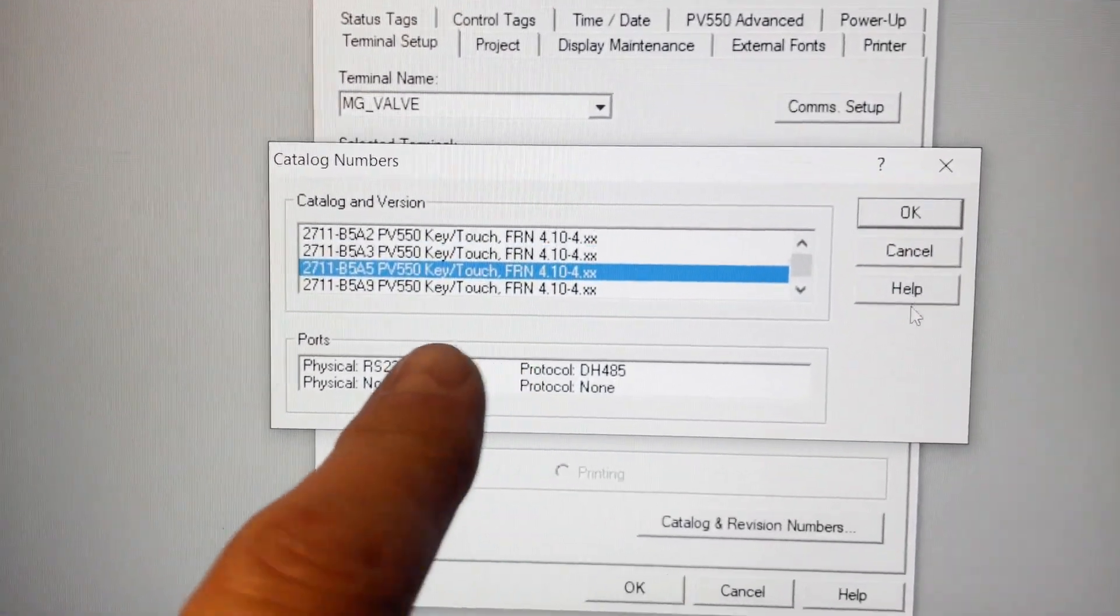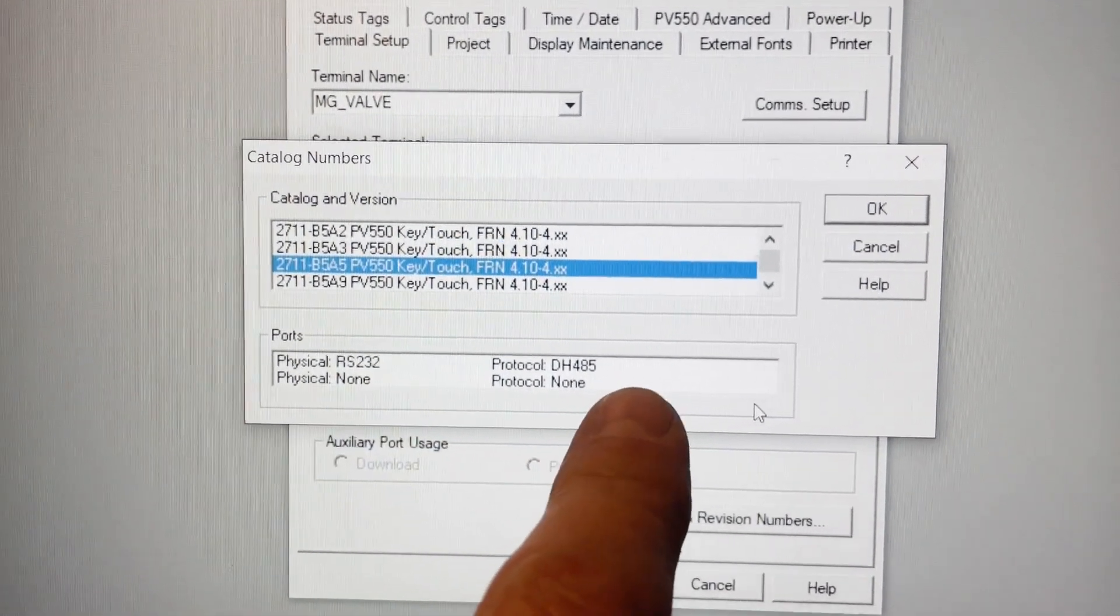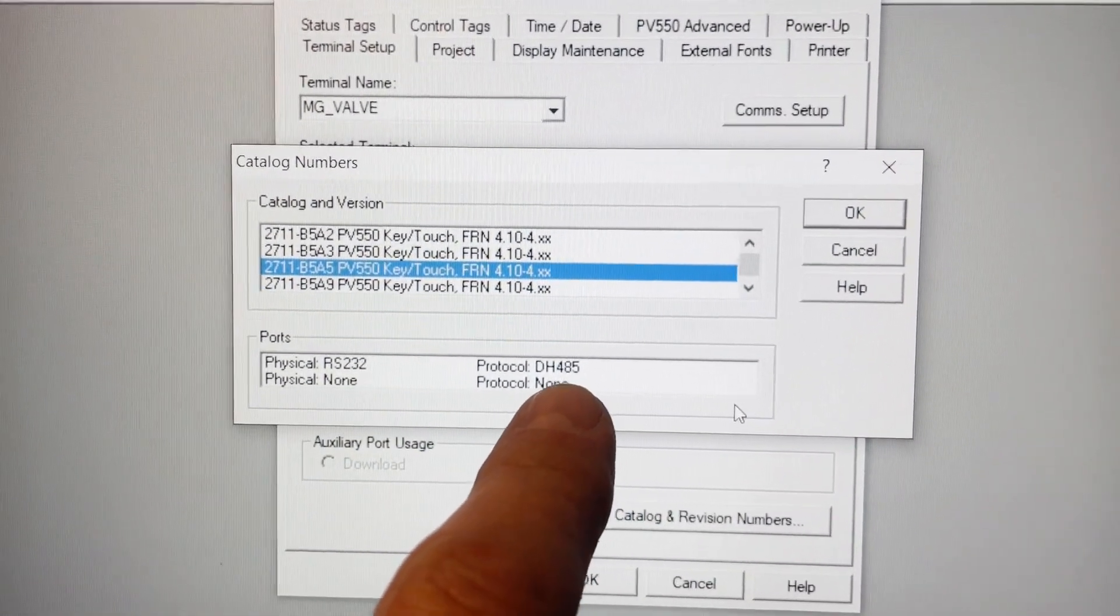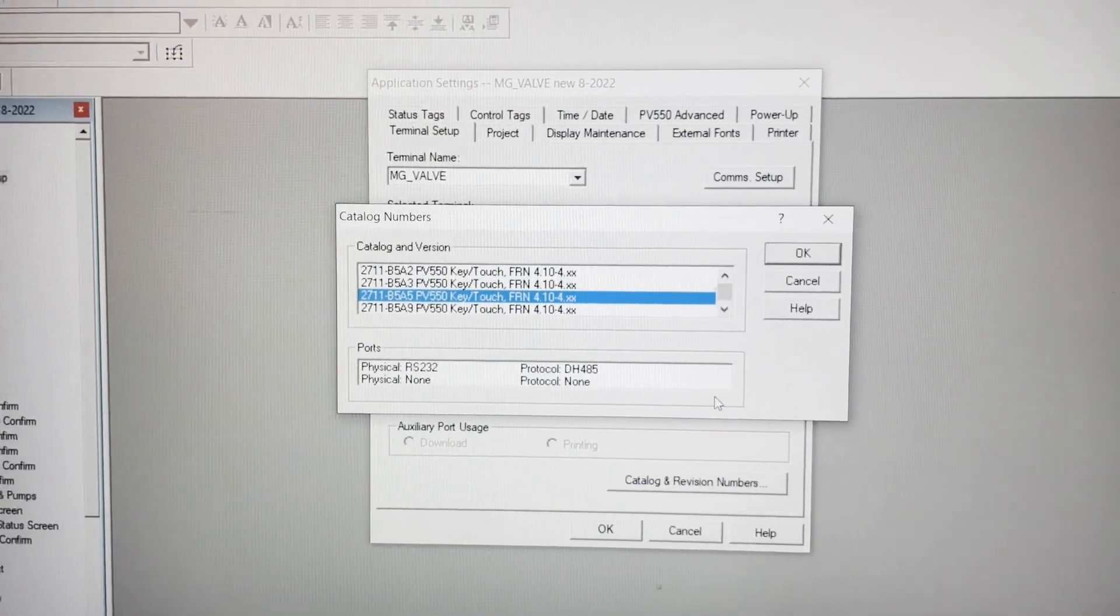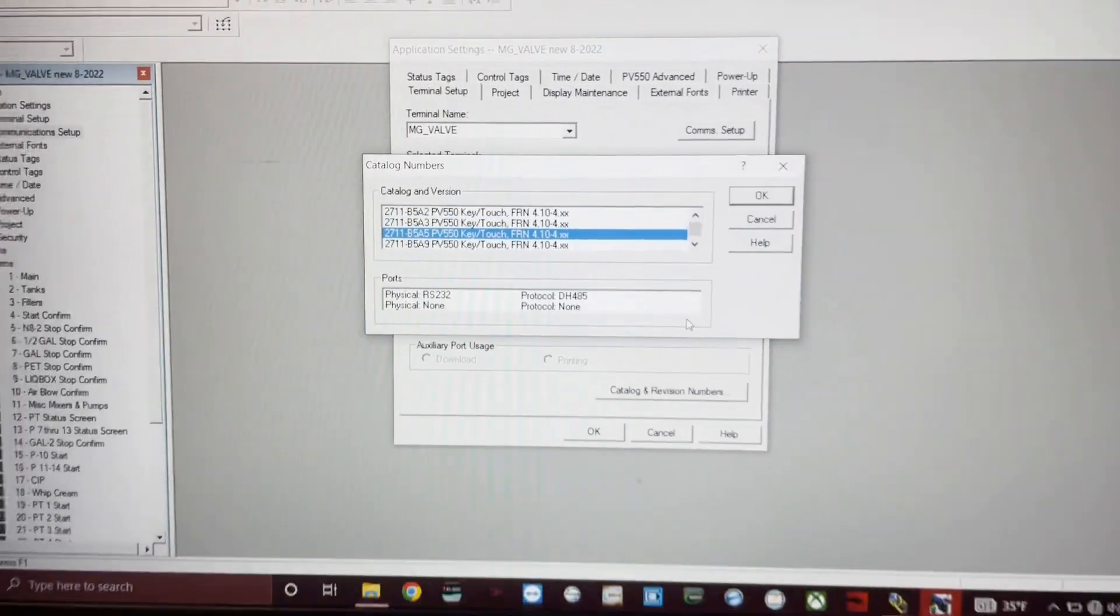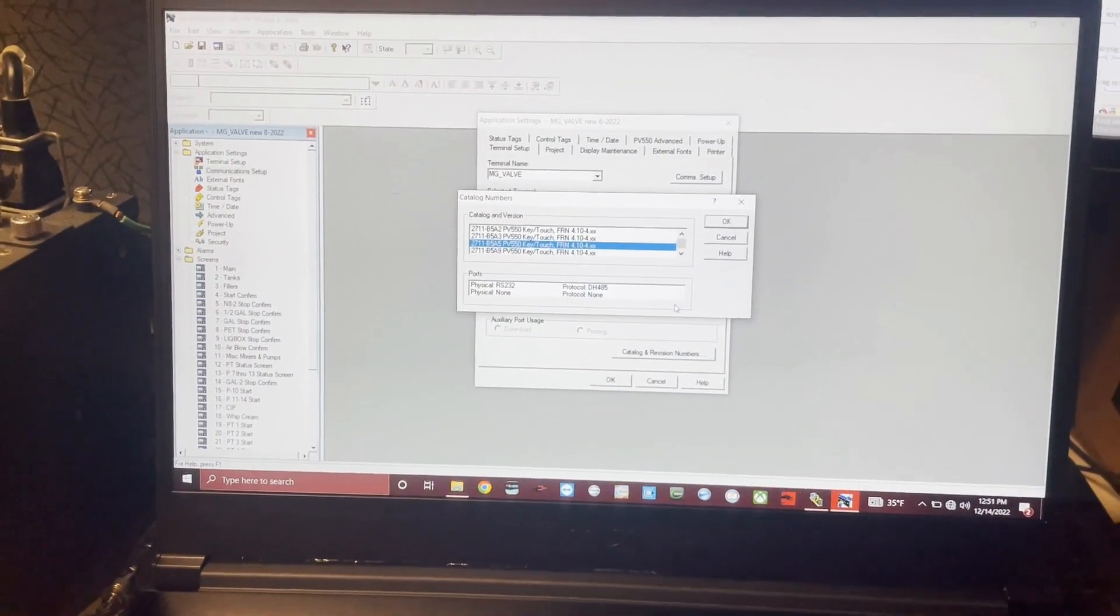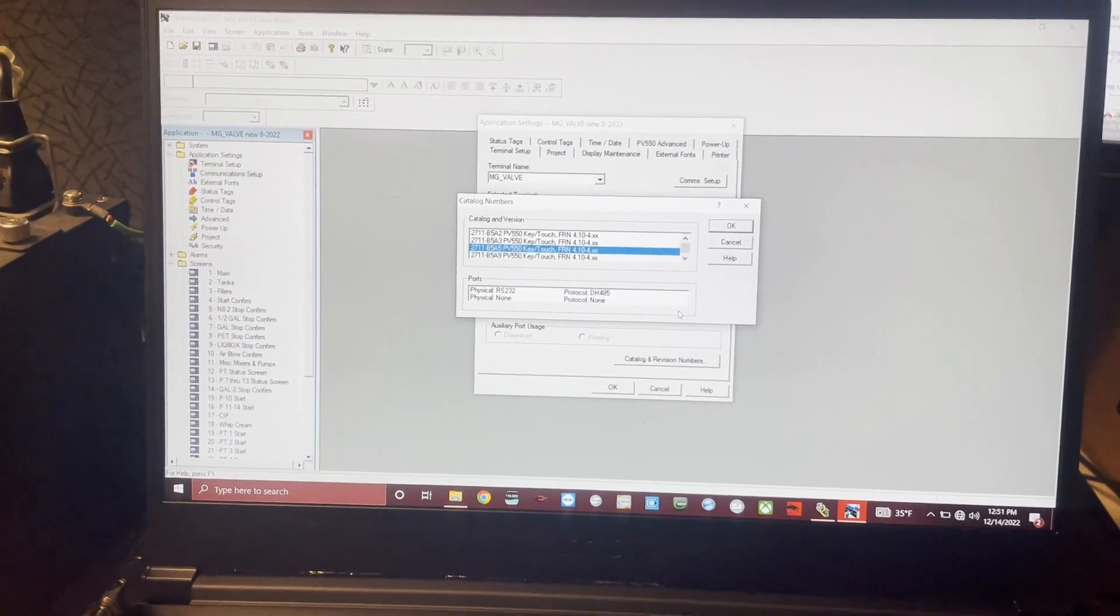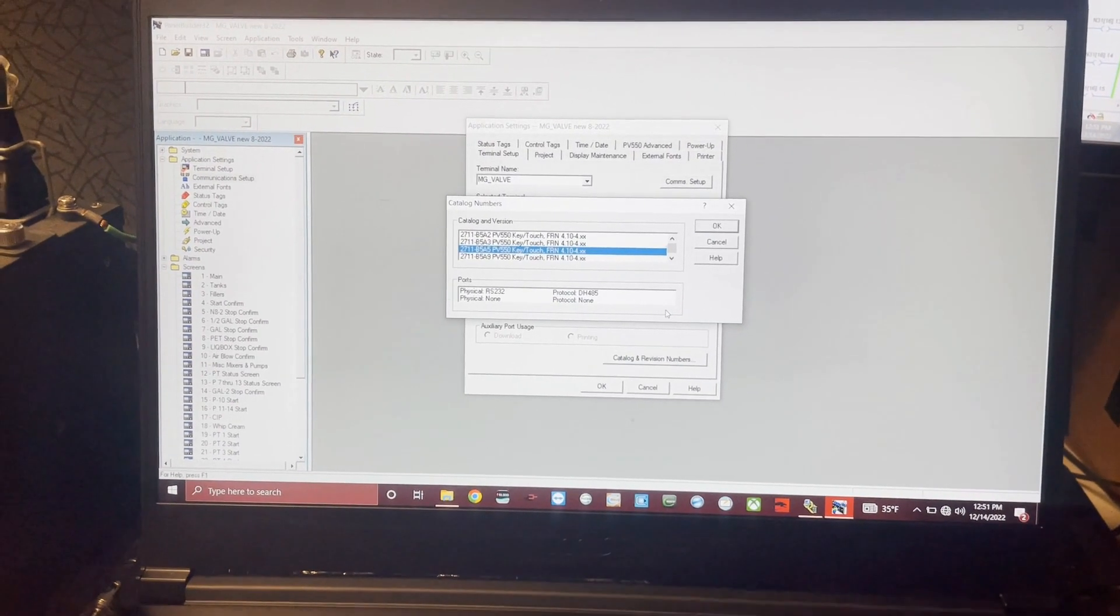You can see down here the physical port is RS-232. The protocol is DH-485, and the 550s are a little bit different if you're trying to use this. This is a Windows 10 machine, and we're going to go through what you need to connect to it.